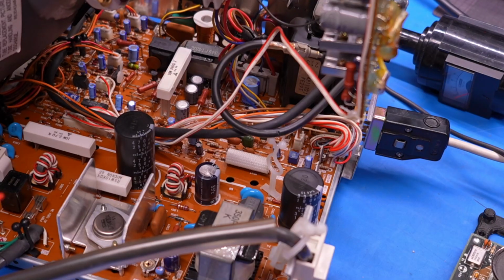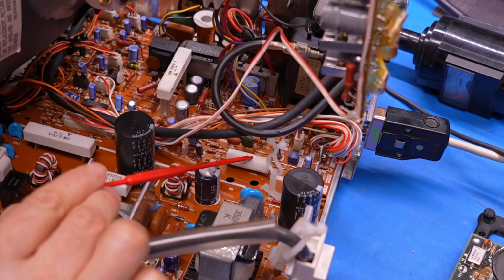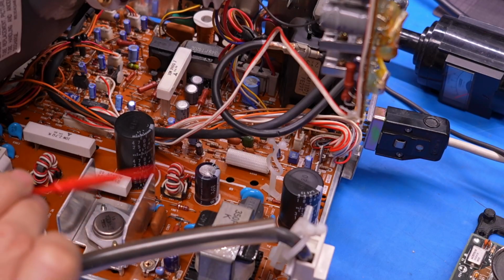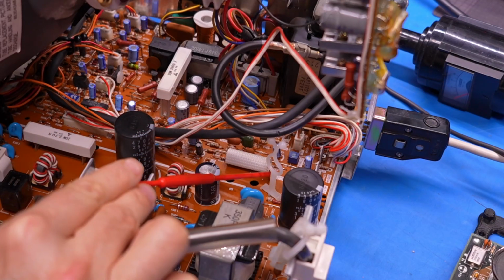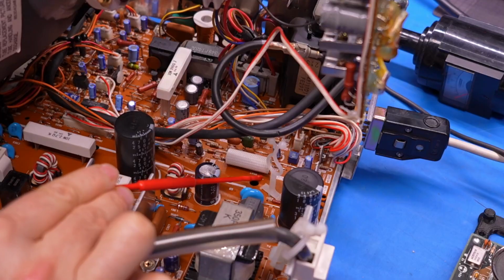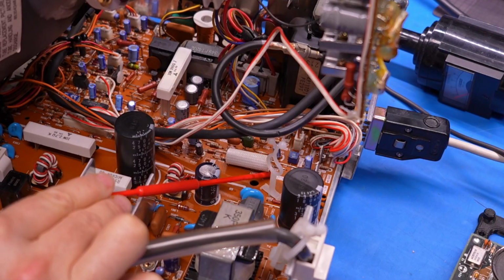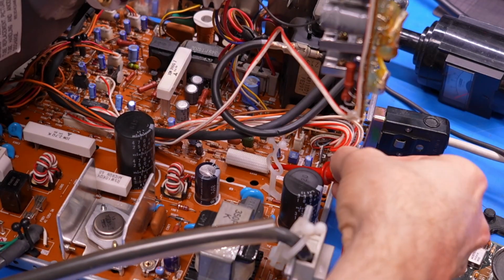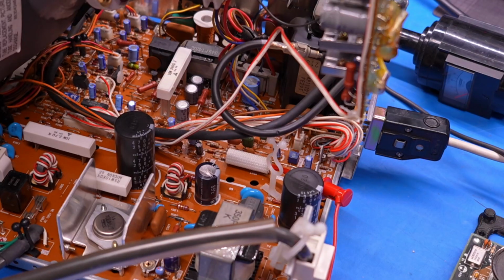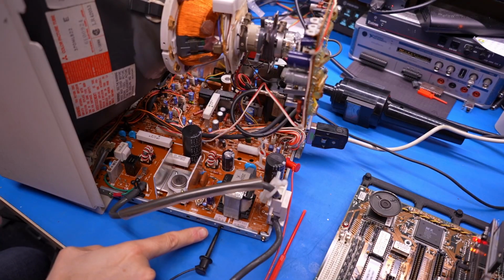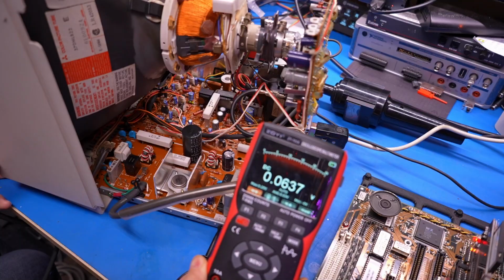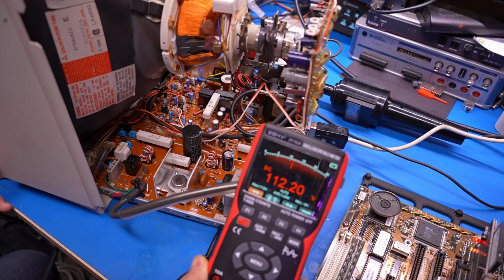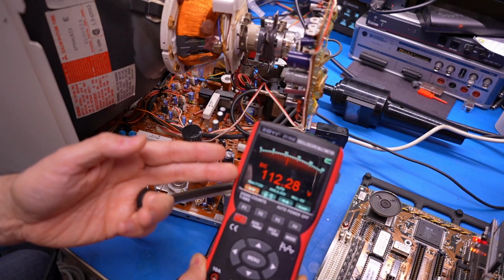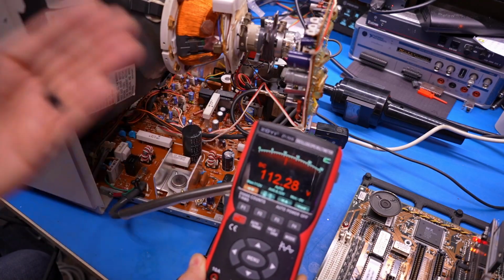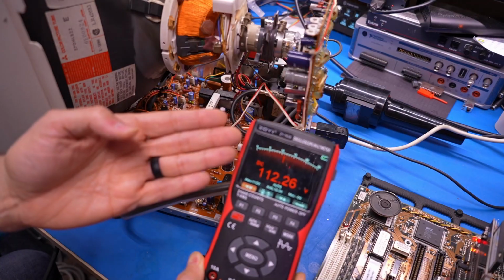So the service manual for this monitor tells you how to check the B plus, but this is a resistor here that connects the power supply to the rest of the monitor. And there's a pin on the right side there, just where the red pointer stick is. That's the B+ test point. And we'll just hook onto that with the probe there. And I have the other probe just connected to the chassis ground right here. And if I turn on the monitor, 112.2 volts. The service manual says it should be 112 plus or minus 1 volt. So I'm going to say that B plus is looking perfect.